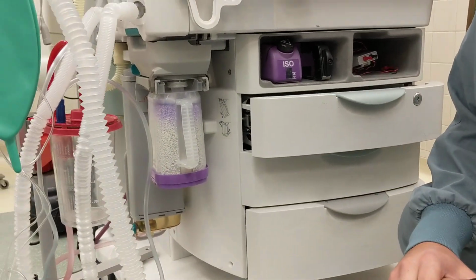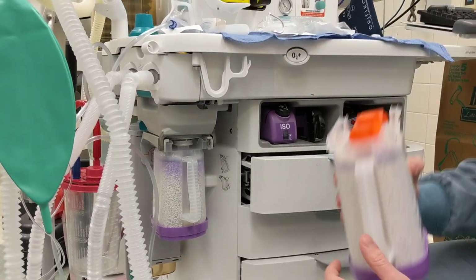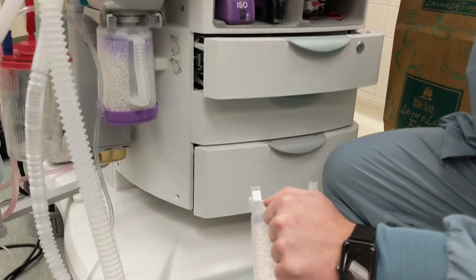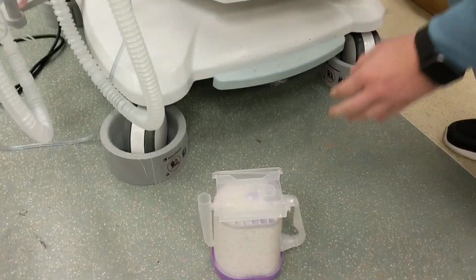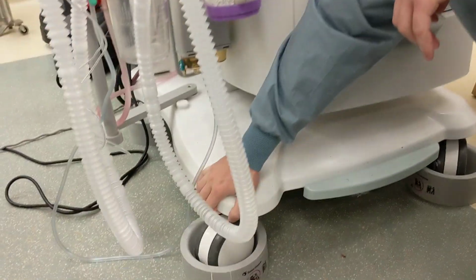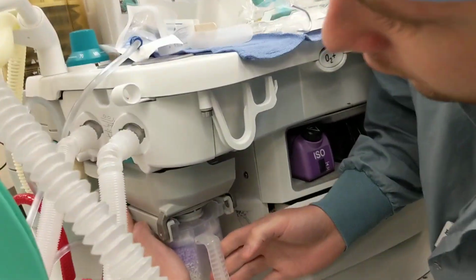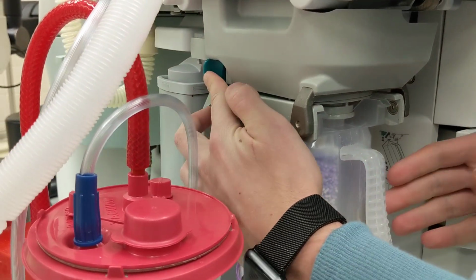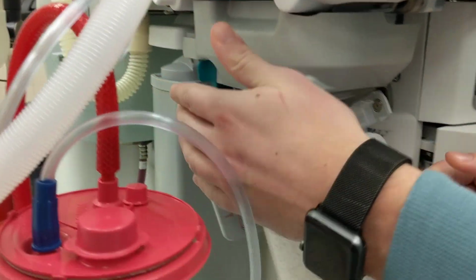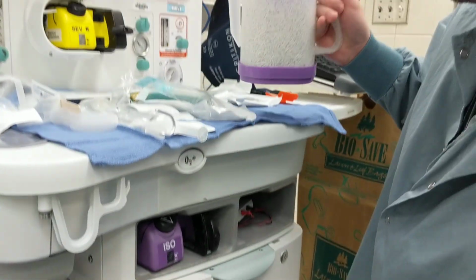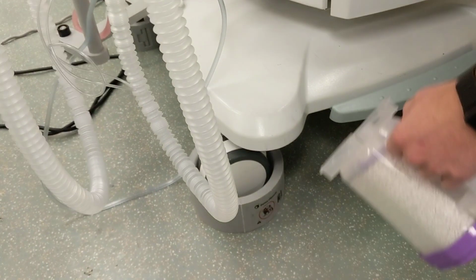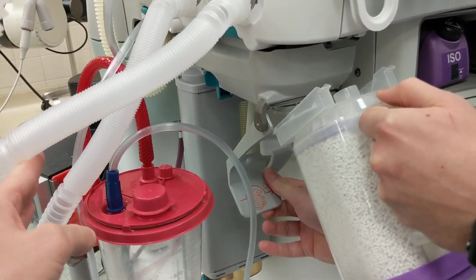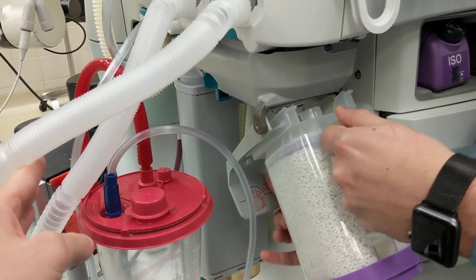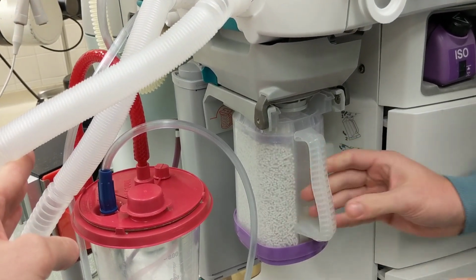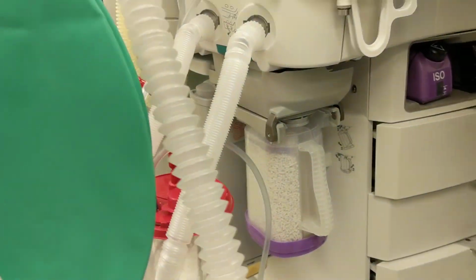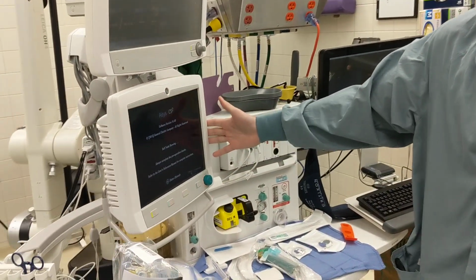This one looks like it's been a little used here, so we're going to go ahead and change this one out before we do the checkoff so we can make sure that the new one doesn't have any cracks or leaks in it. So to take this one out, you come over on the side, and there's a latch here that you can drop down, and that'll release your old one. Slide it out. Put the new one on by the handle, just at an angle, making sure to line it up. And once it seats, give it a little click into place. During that time, the machine will be turning on.